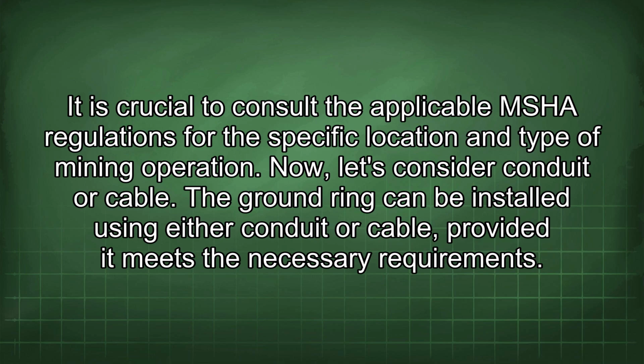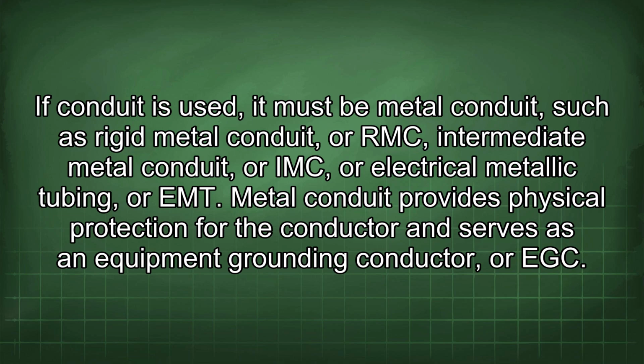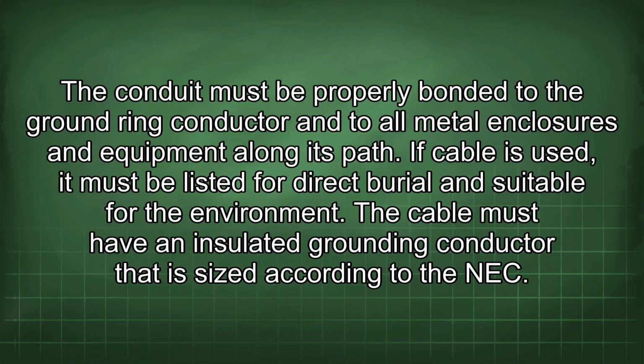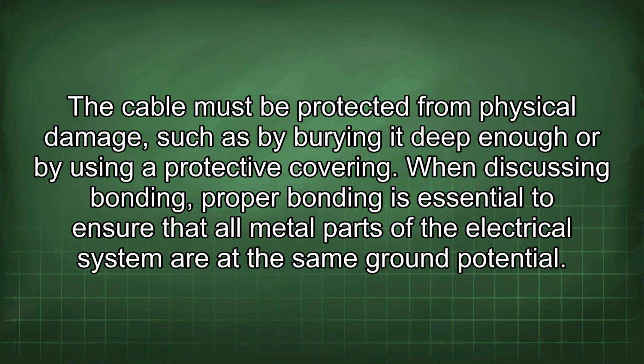Now let's consider conduit or cable. The ground ring can be installed using either conduit or cable, provided it meets the necessary requirements. If conduit is used, it must be metal conduit, such as rigid metal conduit, or RMC, intermediate metal conduit, or IMC, or electrical metallic tubing, or EMT. Metal conduit provides physical protection for the conductor and serves as an equipment grounding conductor, or EGC. The conduit must be properly bonded to the ground ring conductor and to all metal enclosures and equipment along its path. If cable is used, it must be listed for direct burial and suitable for the environment. The cable must have an insulated grounding conductor that is sized according to the NEC. The cable must be protected from physical damage, such as by burying it deep enough or by using a protective covering.